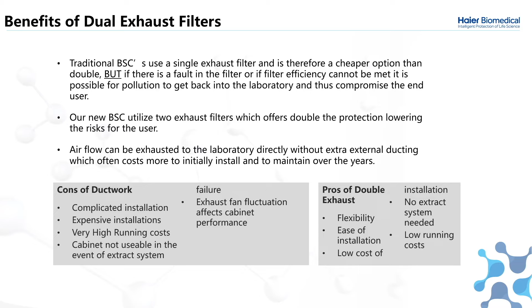In the UK, dual HEPAs are almost standard at all universities where you're working in any hazard group 2 and above. Here are some key selling points for the dual HEPA exhaust. With the dual HEPA exhaust, there are glass side windows which allow natural light inside the cabinet. This helps increase visibility and prevents the user from feeling boxed in when they're using the cabinet for a long time. The dual HEPA exhausts allow for an increased filter efficiency. The airflow you exhaust is basically disconnected from ductwork, as you have that extra HEPA filter protecting the cabinet. You also help ensure user safety, which can be a great selling point, and it's a fantastic selling point here in the UK.